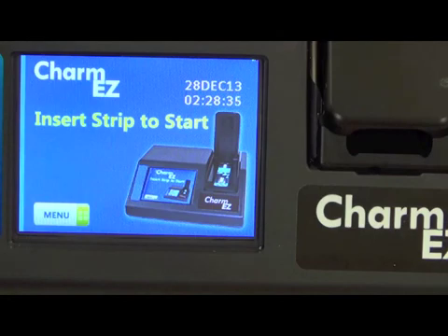This instructional video will discuss changing the option on the EZ Reader from the typical or standard incubate and read mode to a mode where you can just use the reader as a reader only to interpret the results of a strip.